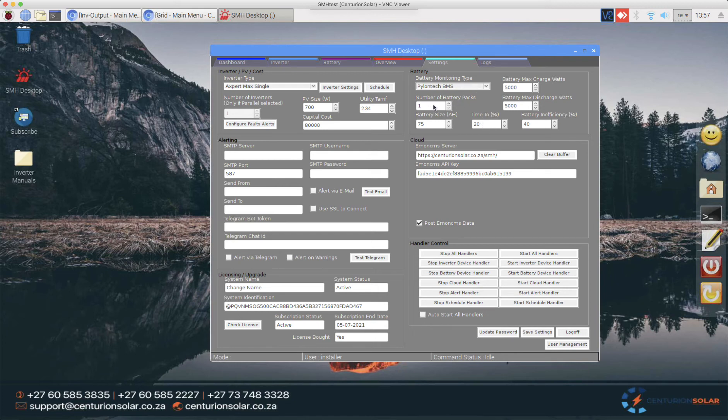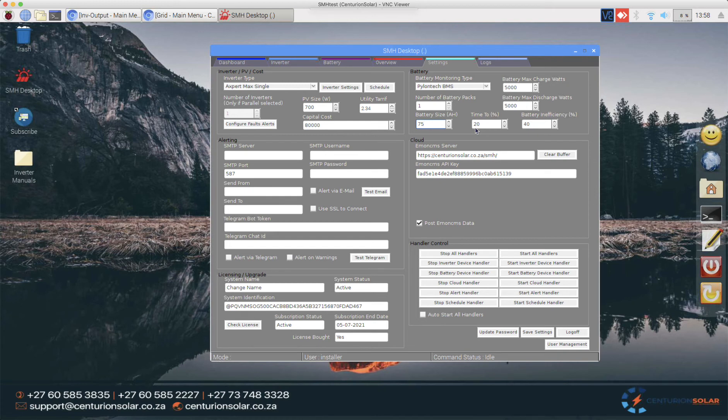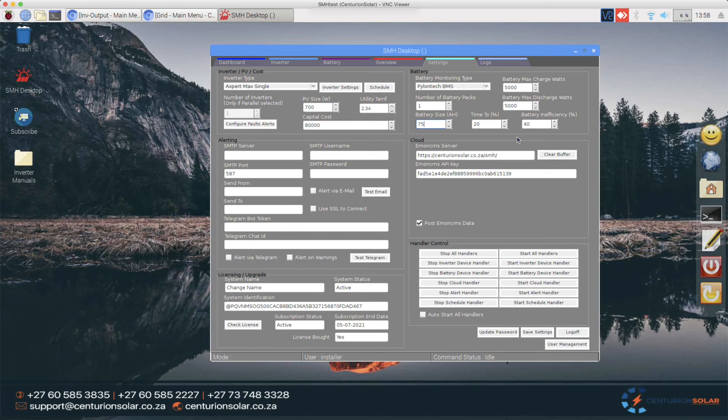Then I only have one battery connected here and it's a 75 amp hour battery. I also would like to see how much time do I have to run this battery until it gets to 20 percent. So because we have the BMS that we can talk to directly and we know what the battery inefficiency is in this case 40 percent which is about standard for most lithium batteries. I can then calculate that based on whichever load I'm experiencing how much time do I have before the battery reaches this X percentage which in this case is 20 percent.